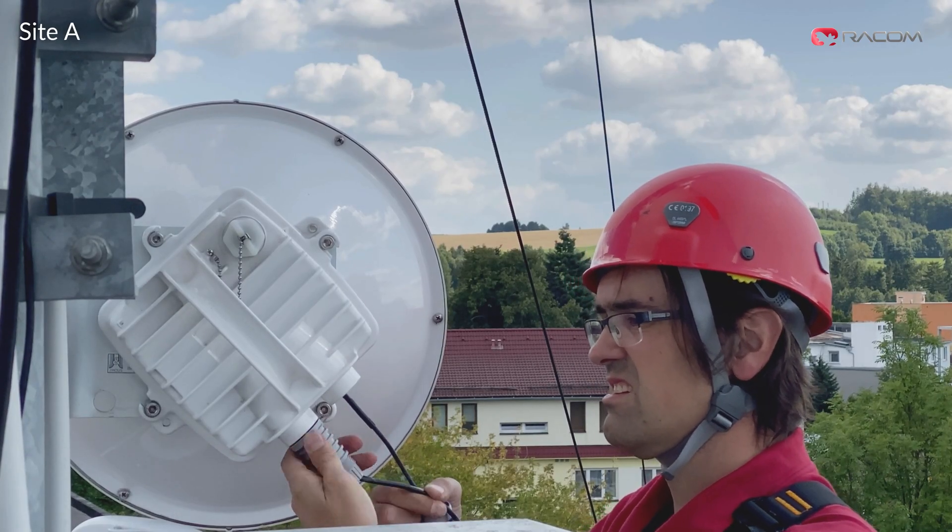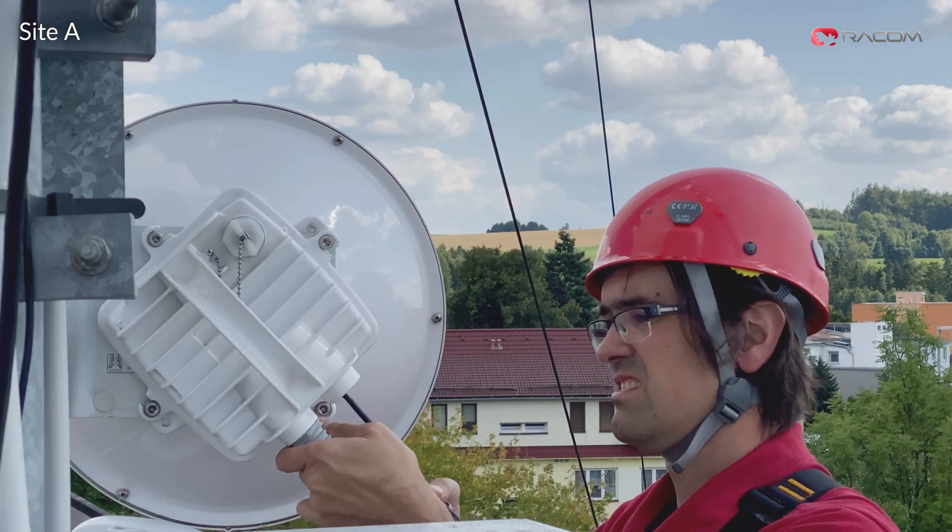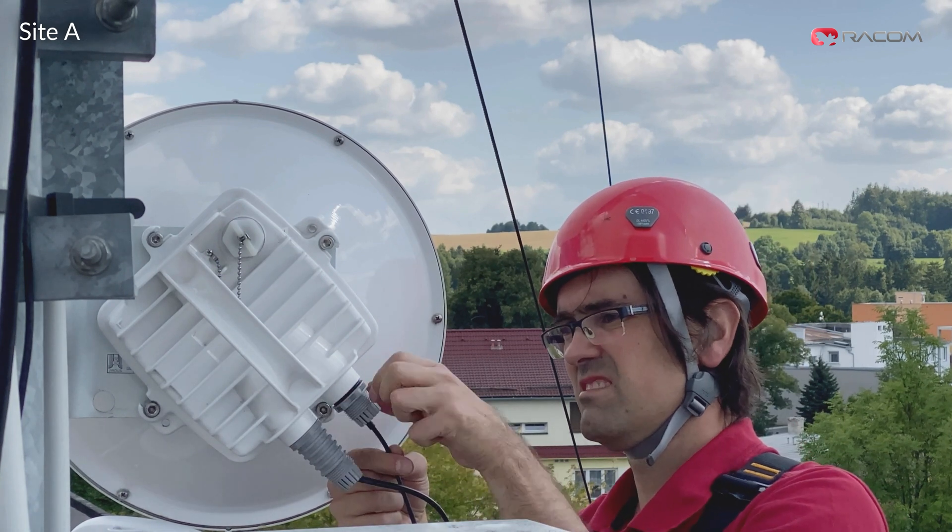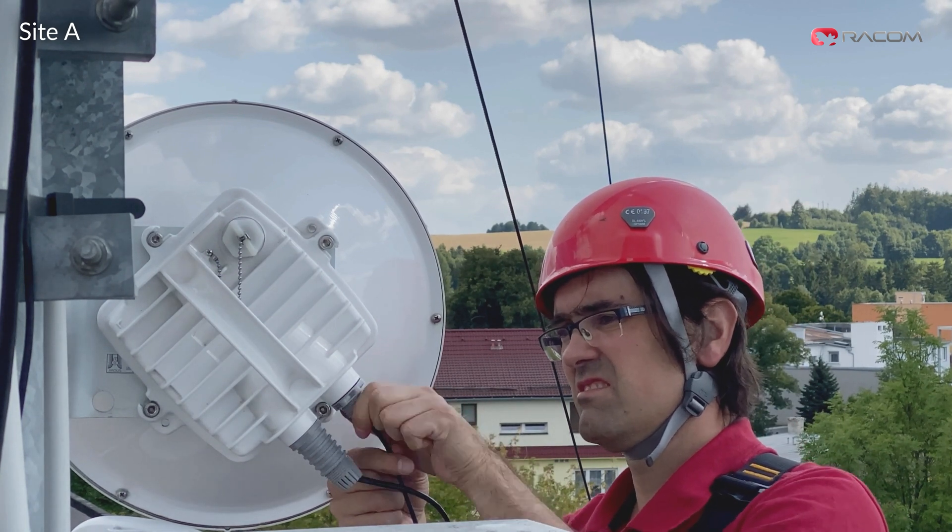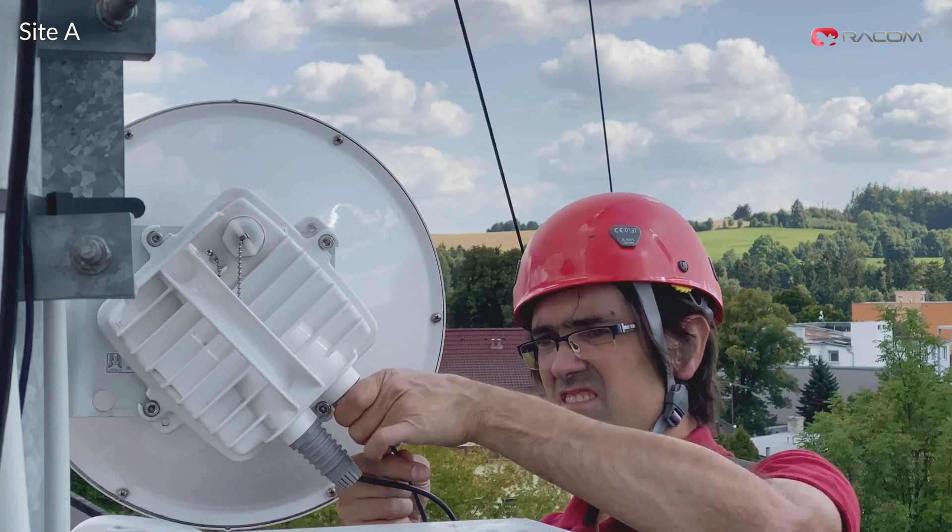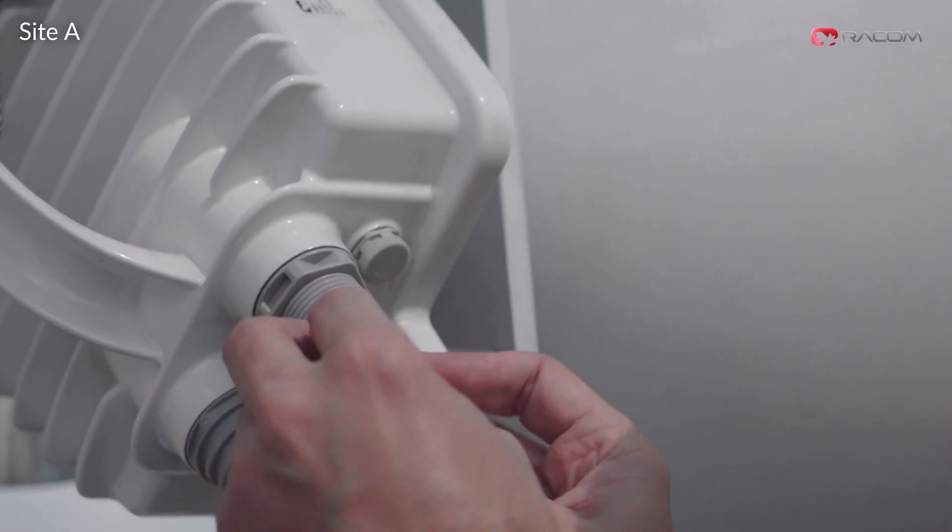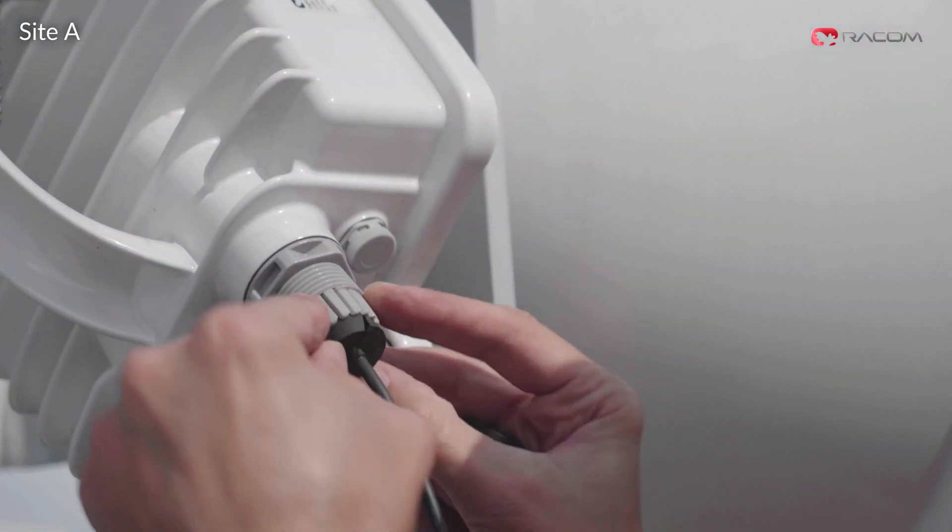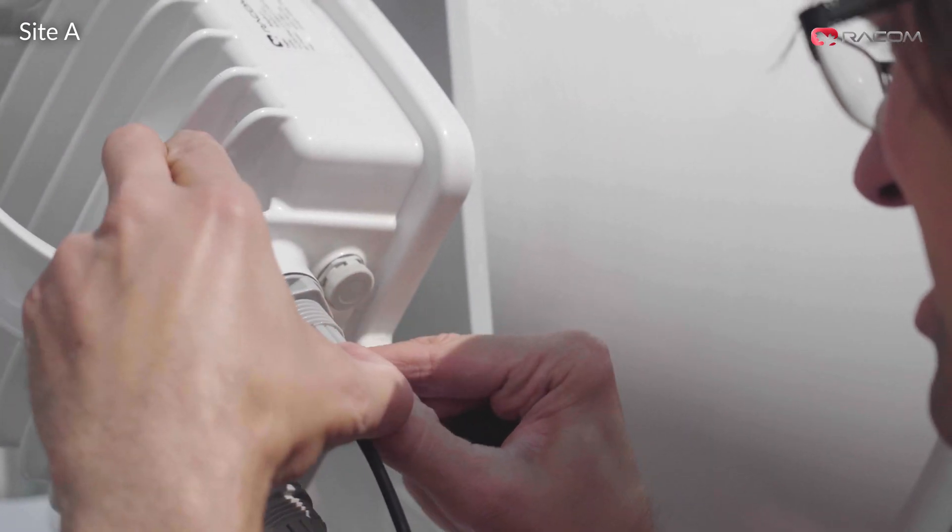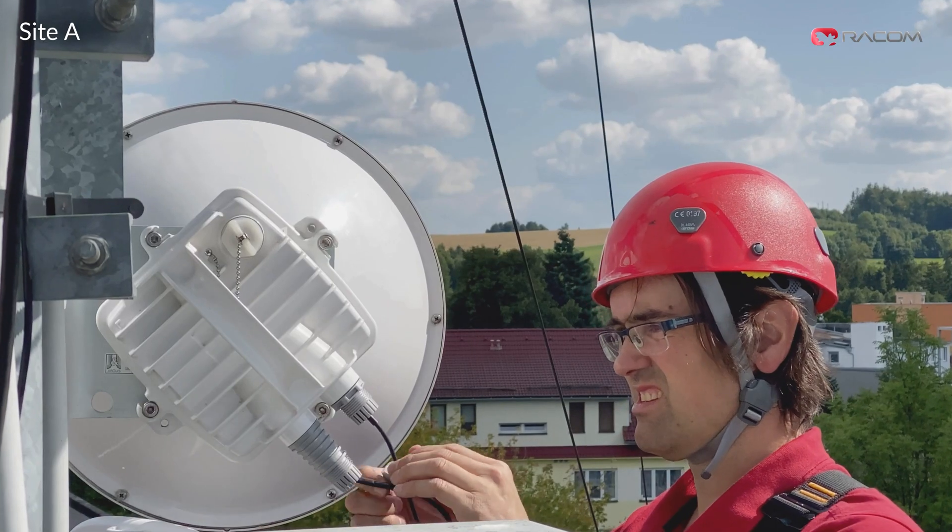Please note that all cables except for optical fiber should be assembled with respective surge protection located before they enter the building. Bear in mind that local legislation or your company standards may require installation of different or additional grounding and surge protection.